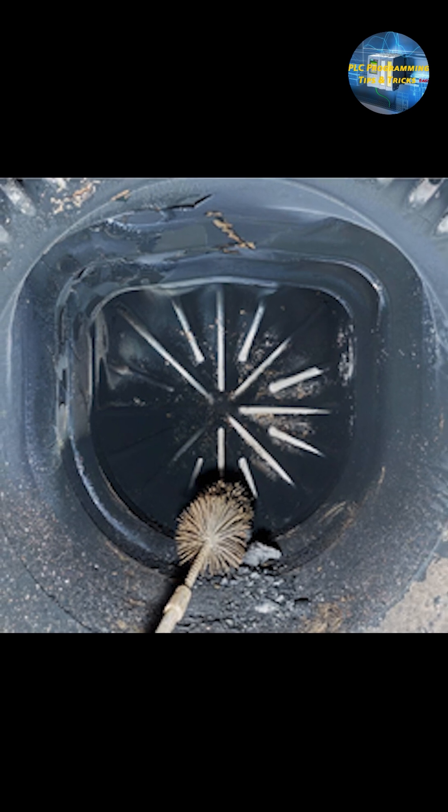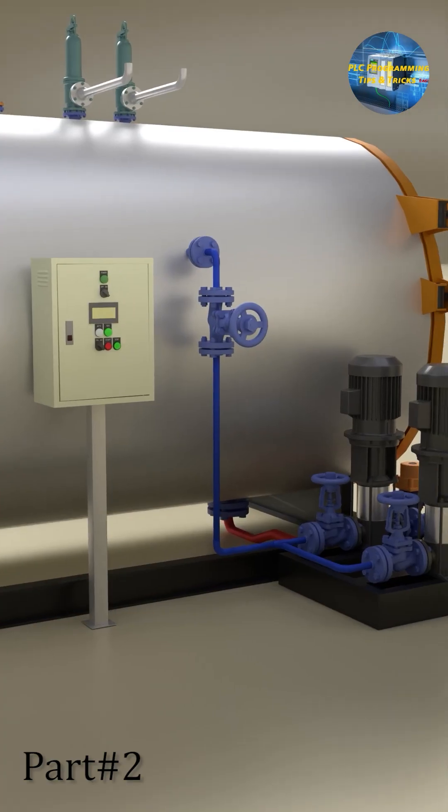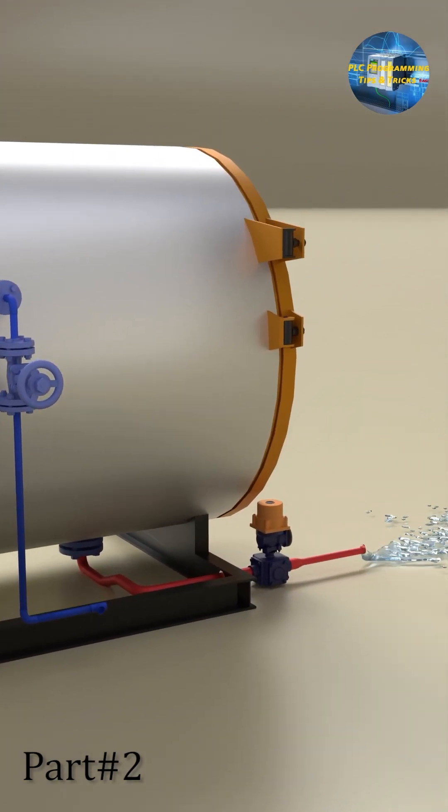These drain valves open maybe 4 to 5 times a day for quick 10 to 20 seconds just to drain some water from the boiler, and this helps to improve the boiler efficiency.